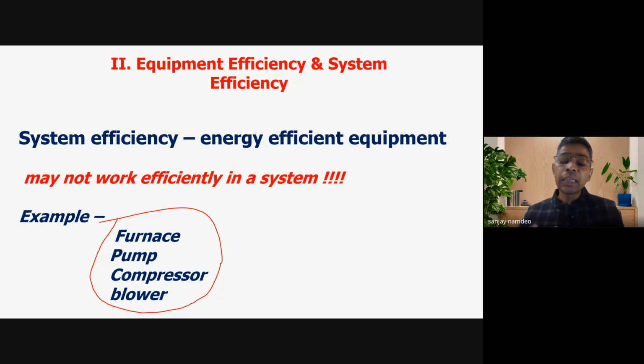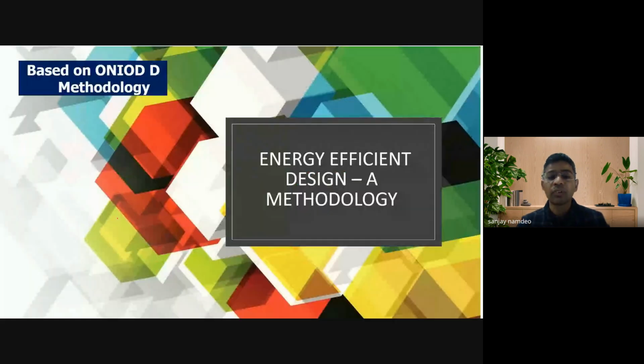If the equipment is not of the correct size, as we have seen in the pump case study, even a 200 kilowatt motor and a 1250 and 42 meter head pump would have been of best efficiency, but when it is not matching my requirement, my system efficiency would be less than the design efficiency. The same is true for any other equipment. If that equipment is not correctly designed to match my requirement, when it comes into operation, it will not operate efficiently.